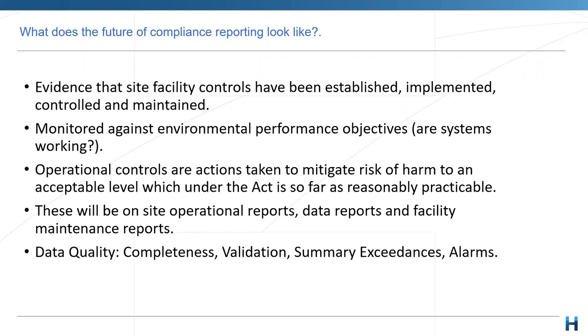So we do some of these sorts of facility monitoring sites for heavy industry where you're looking at a whole lot of metrics which traditionally you would have said are more about operational metrics. And these are very important in the context of showing that you're maintaining these systems. So there's things there like data completeness. So have you measured at the frequency you said you would? Have you validated that data, that it makes sense? And then you have summary reports of exceedances and summary reports of alarms, which show you've been non-compliant.